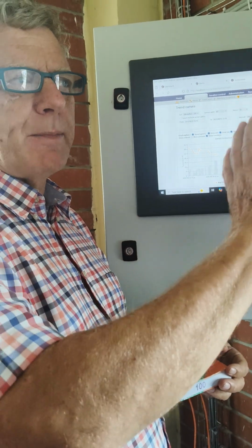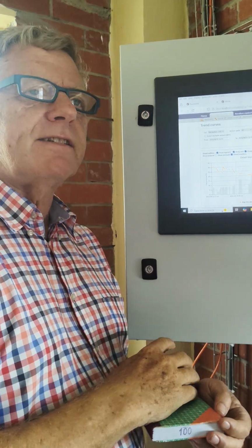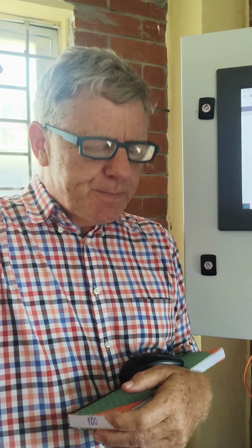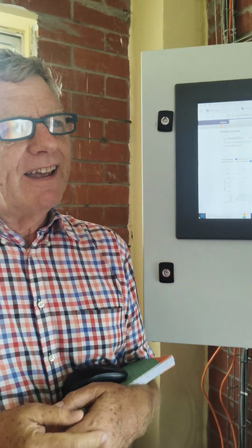I'm not saying anything about the machine because we also do chillers, so I will not. But it's not a bad machine. I can tell you that. It's not the machine, but they don't know about it. The thing is, it doesn't matter that it's raining, because even if you take in high humidity air in the chiller, you cool down the grain to maybe 10 or 15 degrees, whatever. So the dew point of the air will have that temperature, irrespective of sunshine or rain outside. It cannot be influenced.